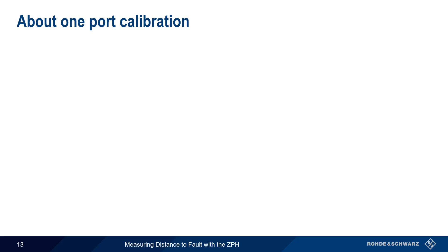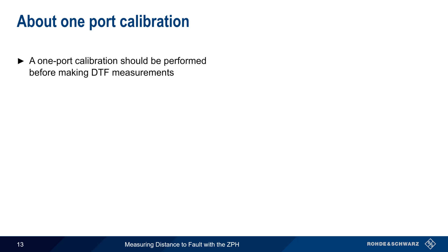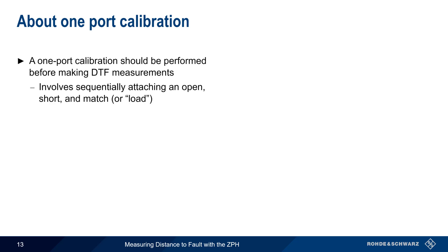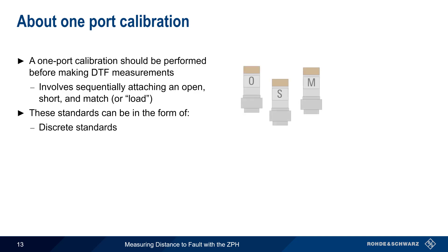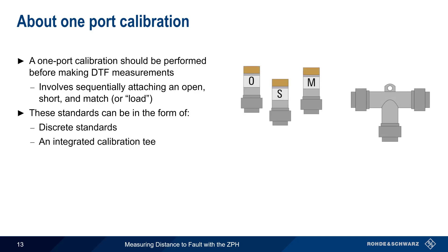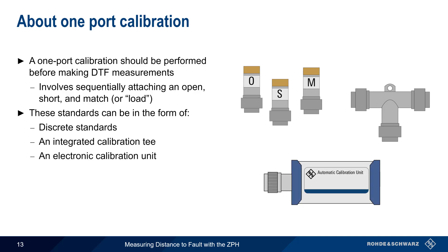After configuring parameters, the next step is to perform a one-port calibration. This process involves sequentially attaching an open, a short, and a match or load to the location where the cable under test will be connected. These standards can be in the form of discrete standards, or may be combined into a calibration T. In addition to these manually attached standards, electronic calibration units can also be used. These units switch their internal standards in and out automatically, and are controlled by the ZPH.